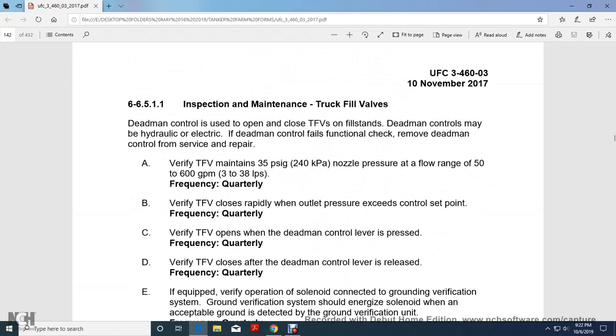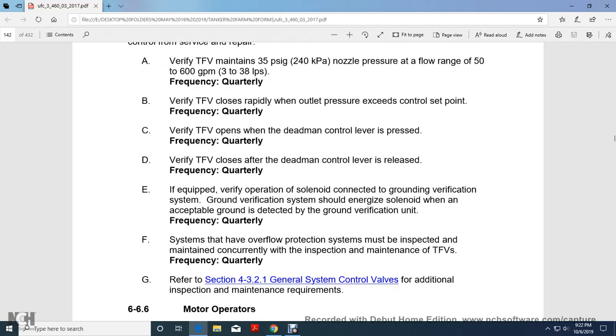6.12 of the truck fill valve. 6.6.5.11, inspection of truck fill valve. The dead man control is usually the open-close control of the truck fill valve. The dead man controls may be hydraulic or electric. If the dead man control fails the function check, remove it from service and repair. The truck fill valve maintains 35 psi gauge nozzle pressure at a flow range of 50 to 600 gallons per minute. Quarterly, verify the truck fill valve closes rapidly when the outlet pressure exceeds the control setting. Verify the truck fill valve opens when the dead man control lever is pressed. Verify the truck fill valve closes after the dead man control is released, quarterly.